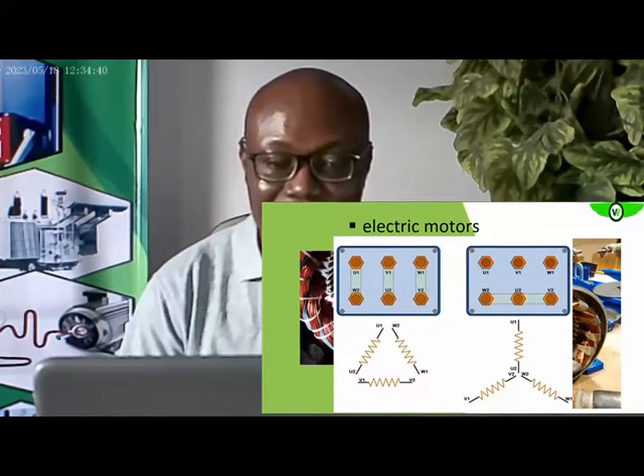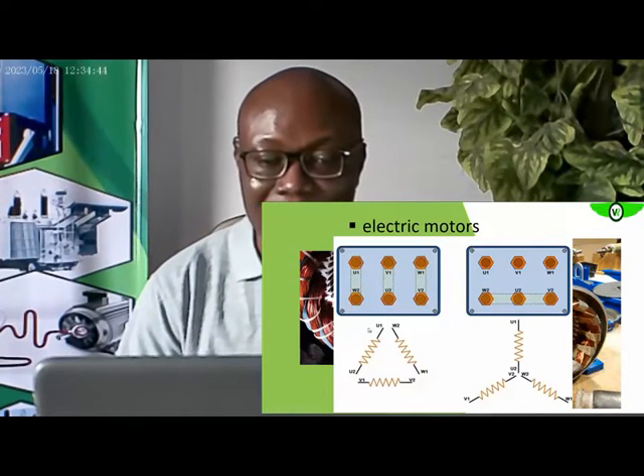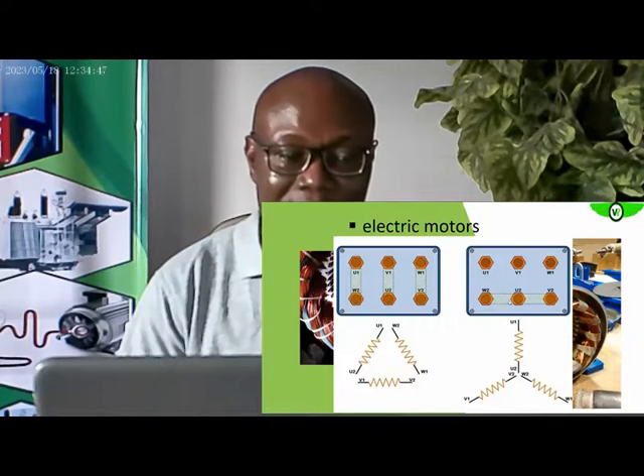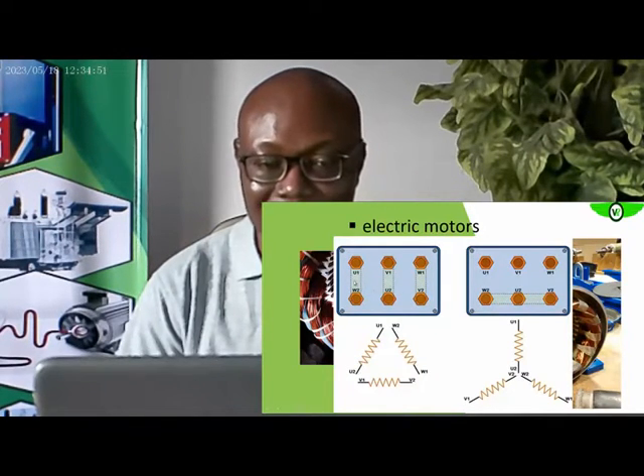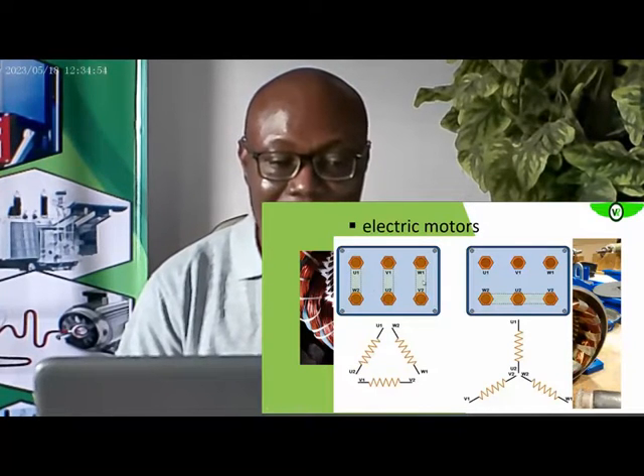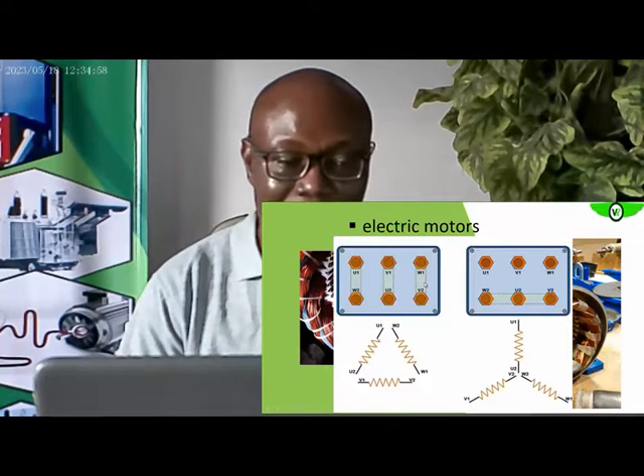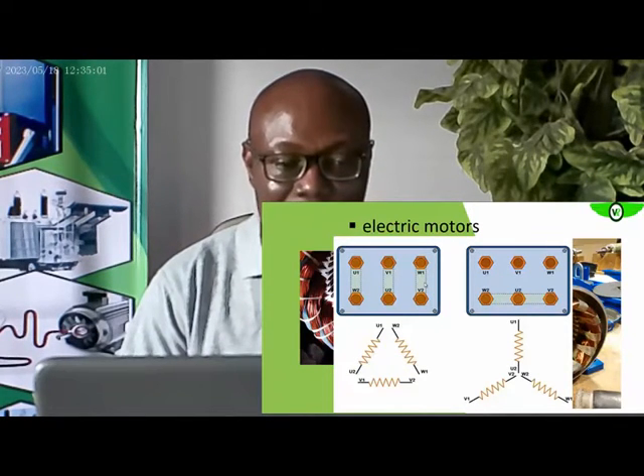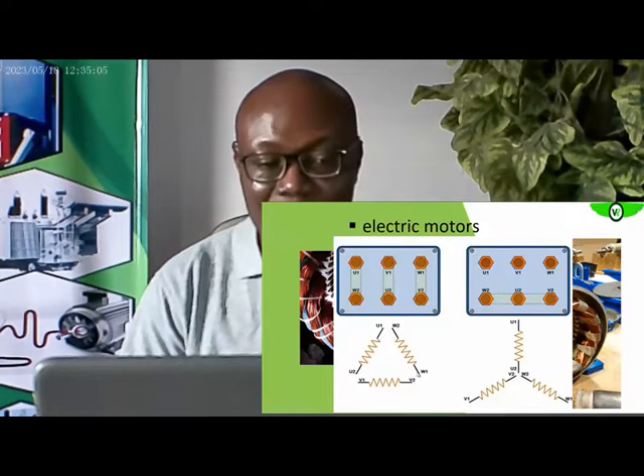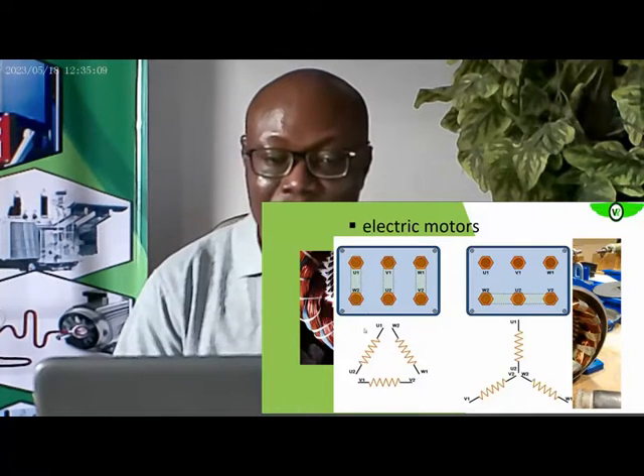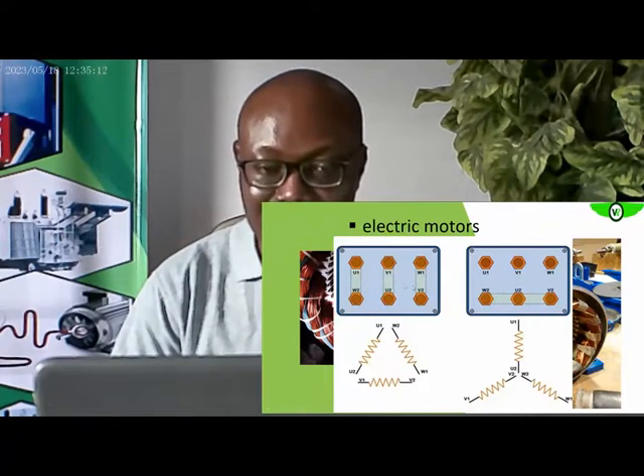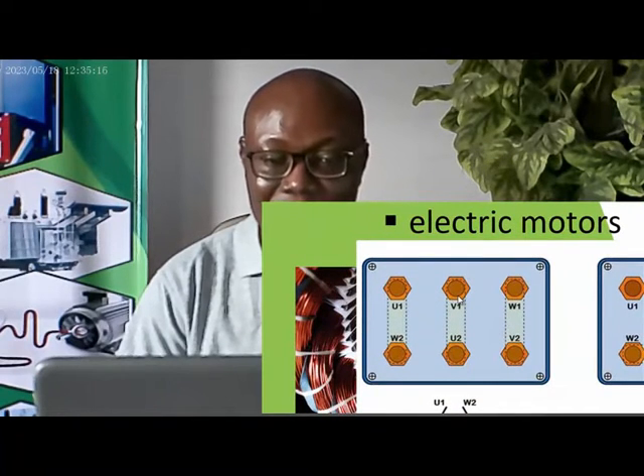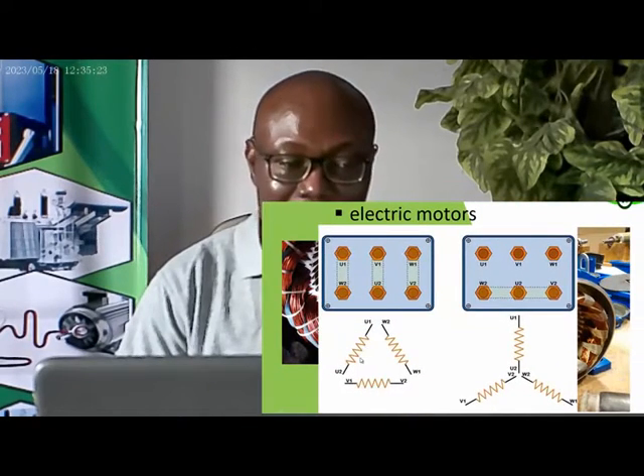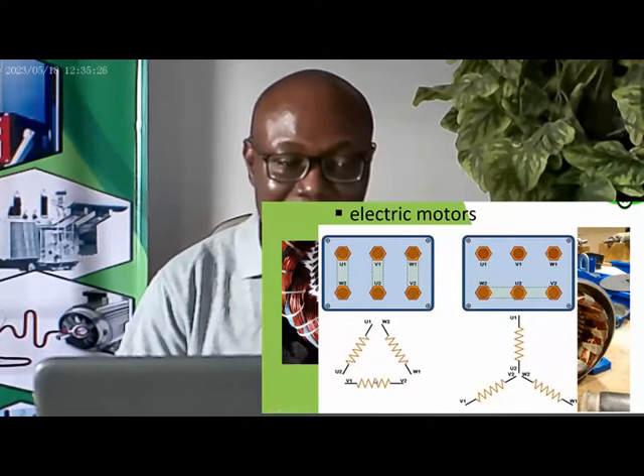Now, if you are testing the insulation between phases, it means that you have to remove these shunting bars on the star point, or the ones that you use to connect your delta. You remove them so that you can separate the winding into individual coils. So W1 and W2 is a single coil, V1 and V2 is a single coil, U1 and U2 is also a single coil, with the 2 on the other side. So if you test between U1 and V1, you are testing the insulation between the U winding and the V winding, which means you are looking at the separation between each of the phases.